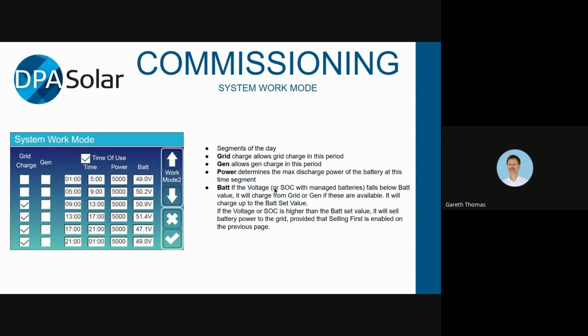Now we come through to the system work mode, time of use. So this is a menu where it divides the day into a series of segments. You can change these time segments, starting at, that's 1 a.m. to 5 a.m., 5 a.m. to 9. You can click on those and use the up and down arrows on the front of the inverter to change those.